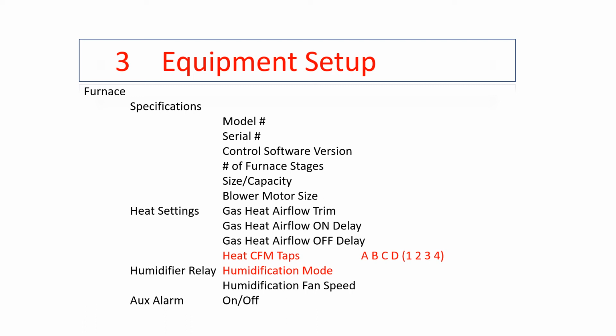So it doesn't auto set a CFM for you. You have to decide where you want it. My best suggestion is to always do a delta T when you do an install, and if you're very comfortable with the temperature rise, that means the setting is fine. We also have the humidifier relay located in the furnace on the board. We'll have to switch it on here, and we'll have to tell it when to humidify or what our fan speed is at this point.